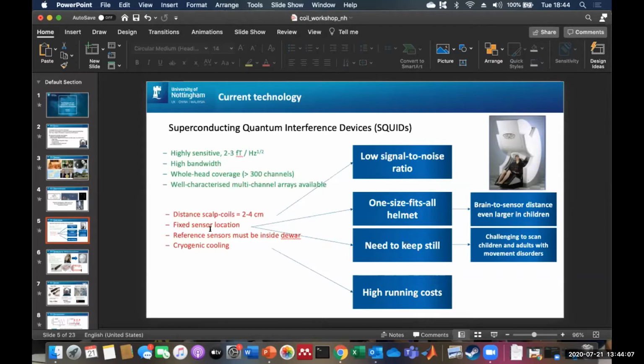There are issues with SQUID-based MEG, is that the distance from the scalp to the coils is quite large, and as the signals decay with a 1/r cubed, we have a low signal to noise ratio. There's also a fixed sensor locations. This means we have a one-size-fits-all helmet, which makes that source to sensor distance even larger in children, meaning that it's difficult to scan them and understand the brain in the developing adult.